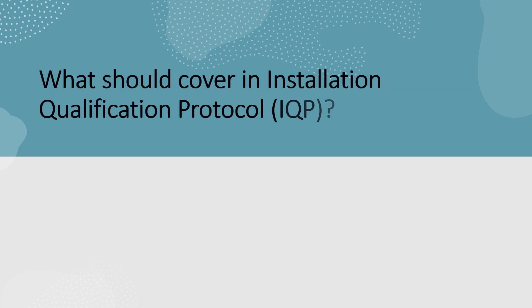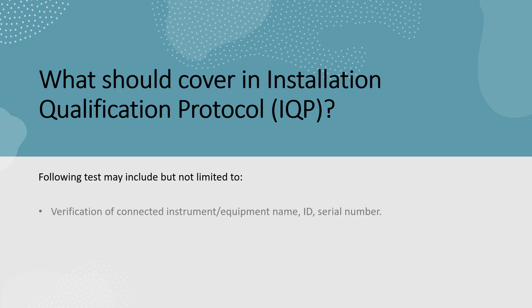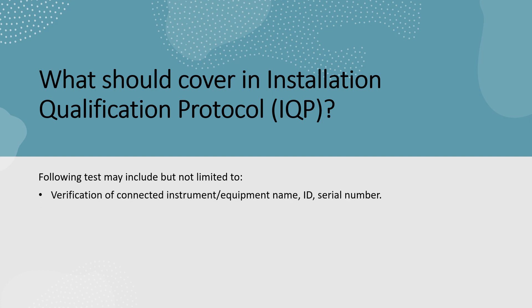So now in this slide, we will discuss what should be covered in the installation qualification protocol, that is called IQP. The following tests may include but are not limited to: first, verification of connected instrument or equipment name, ID, and serial number. For example, instrument name is HPLC or UV spectrophotometer. There will be some in-house procedures available to assign an identification number to the hardware, and the serial number which is mentioned on the hardware or manufacturer document.